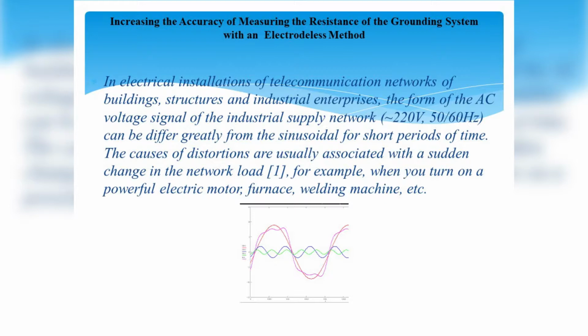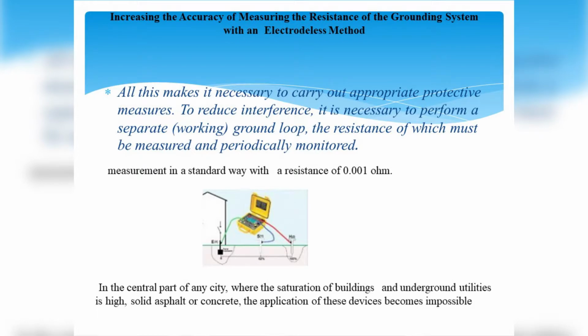To reduce interference, it is necessary to perform a separate working ground loop, the resistance of which must be measured and periodically monitored. There are devices that allow an electrodeless method to monitor and evaluate the resistance of the ground loop, but these devices have a greater measurement error than devices that measure the resistance of the earth electrode by the electrode method. The article deals with existing instruments CA6410, MZC303E, which can evaluate the resistance of the earth electrode, and the possibility of increasing the accuracy of the measurement with the help of special current clamps, which are shown.